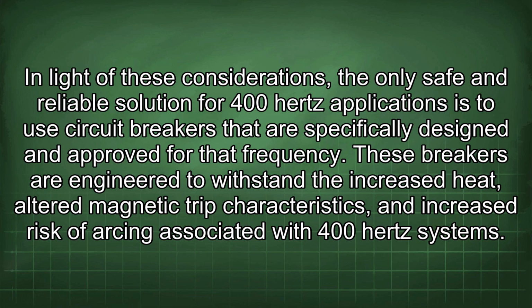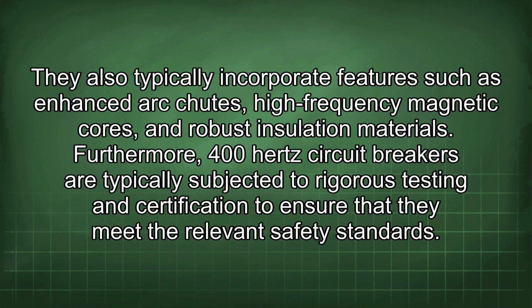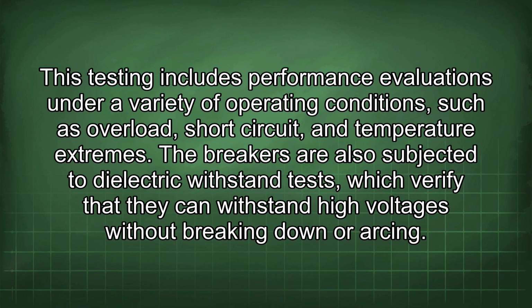These breakers are engineered to withstand the increased heat, altered magnetic trip characteristics, and increased risk of arcing associated with 400 Hz systems. They also typically incorporate features such as enhanced arc chutes, high-frequency magnetic cores, and robust insulation materials. Furthermore, 400 Hz circuit breakers are typically subjected to rigorous testing and certification to ensure that they meet the relevant safety standards. This testing includes performance evaluations under a variety of operating conditions such as overload, short circuit, and temperature extremes.